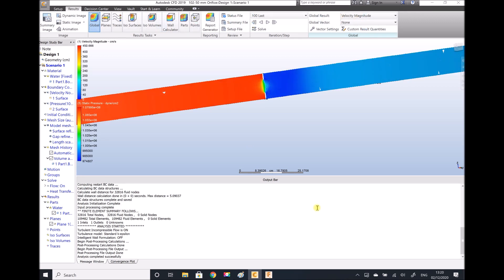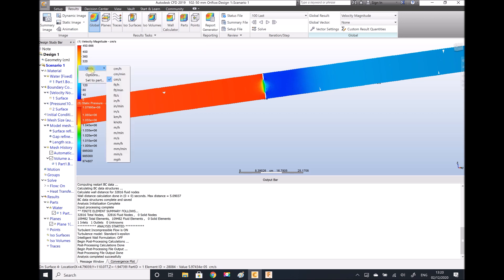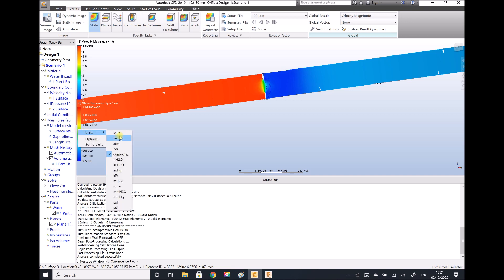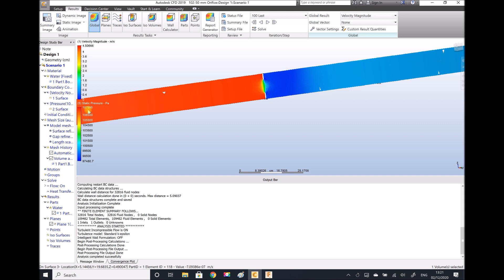Our second simulation took perhaps five minutes to run. What we notice is that our results have changed somewhat. If we look at our velocities, switching units to metres per second, our maximum velocity has increased to 4.5 metres per second through the orifice. And looking at pressures, we have 107,995 Pascals before the orifice and 97,481 Pascals after the orifice. This time the pressure drop across the orifice is 10,514 Pascals — a reasonable increase from the previous value of around 8,300 Pascals.